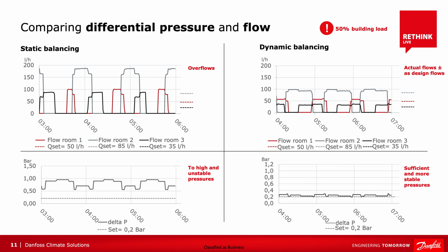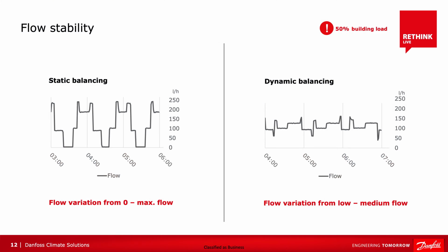What that means is that at that 50% load, we're going to get better performance and have fewer changes to the conditions at the heat pump itself. Once again, flow stability. We want to make sure that our entire hydronic system, including the heat pump itself, has the least amount of variation. With static balancing, we are seeing flow variations from 0 to max flow. Think about getting in your car, putting it in drive, putting the gas pedal all the way down, and then when you see a stoplight, taking your foot off and slamming on the brake at the same time. It's not how things work in real life. With dynamic balancing, the flow variation is from low to medium flow, which is how we drive in a 35 mile per hour zone every day of our lives.